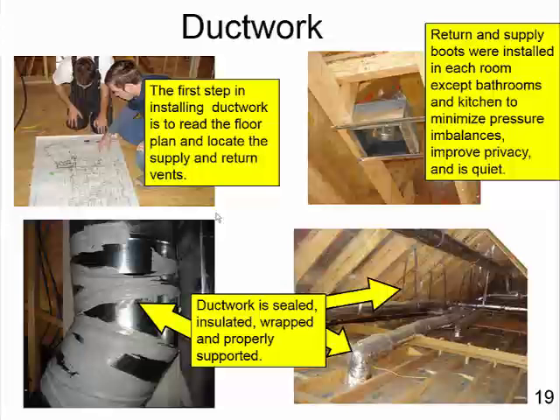The ductwork is all installed because it is a new construction. All the ductwork was sealed, and then it was wrapped and properly supported. You see the support members there. The return and supply vents were installed in each room except bathrooms and kitchen to minimize pressure imbalances, improve privacy, and be quiet. So each room has a return and supply. It's a big house.